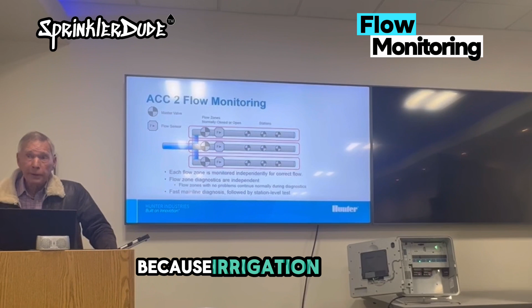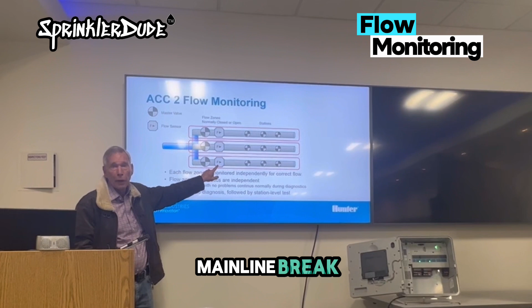If it sees high flow, the first thing it does is shut off all the stations that were running for a minute, and waits to see if the flow drops. Because if you shut off all those zones and the flow doesn't drop, what does that tell you? Mainline break - that's bad. So it shuts down the master valve right then and sends an SMS text to your phone.